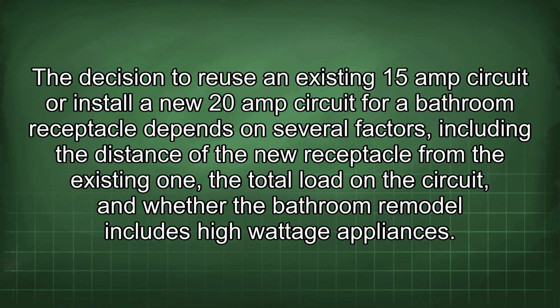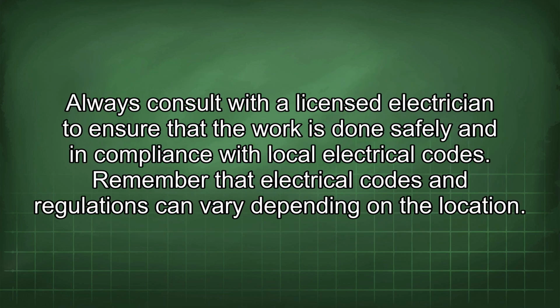The decision to reuse an existing 15-amp circuit or install a new 20-amp circuit for a bathroom receptacle depends on several factors, including the distance of the new receptacle from the existing one, the total load on the circuit, and whether the bathroom remodel includes high-wattage appliances. Always consult with a licensed electrician to ensure that the work is done safely and in compliance with local electrical codes. Remember that electrical codes and regulations can vary depending on the location.